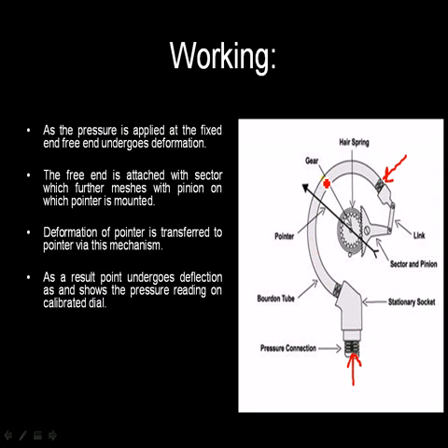Now this tube, being made of elastic material, will tend to uncoil. That is, if this is circular it will try to become straight, slowly and steadily along this dotted line. As the pressure will increase, this will slowly and steadily uncoil like this. When the pressure increases by a bit, then when the pressure is further increased, it will further move like this.